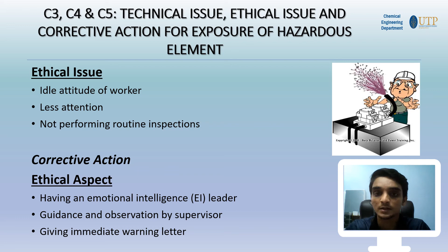The first technical issue is due to failure of the recycle pump for the clarifier, where the clarifier is designed to recycle part of the bottom sludge and another part will be supplied into the sludge tank. Discharge of wastewater is found to exceed BOD limits, which is greater than 50 mg per liter, when the amount of accumulated sludge in the tank increases and is carried together with the wastewater effluent. Corrective action is to consider the process instrumentation system, which has a concentration transmitter at the outlet of the treated wastewater piping and a controller that immediately bypasses the understandard effluent, as well as switches on the backup recycle pump.